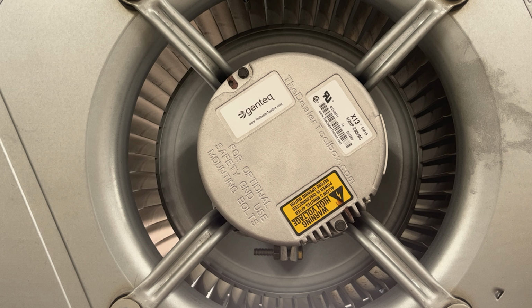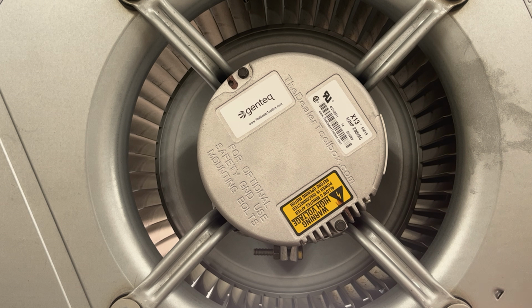And a lot of the times it's either maybe the capacitor's bad inside of here, maybe the board's got a short in it, possibility that the relay's not working, maybe it's stuck in the closed position, maybe it's stuck in the open position. And so you want to make sure that if it's under warranty that you're diagnosing it properly. And some of these manufacturers, they'll give you the entire component below or in module. Sometimes they want to know which components failed and they'll ship you that component. So you want to be accurate on your diagnostic. All right, so stay tuned.